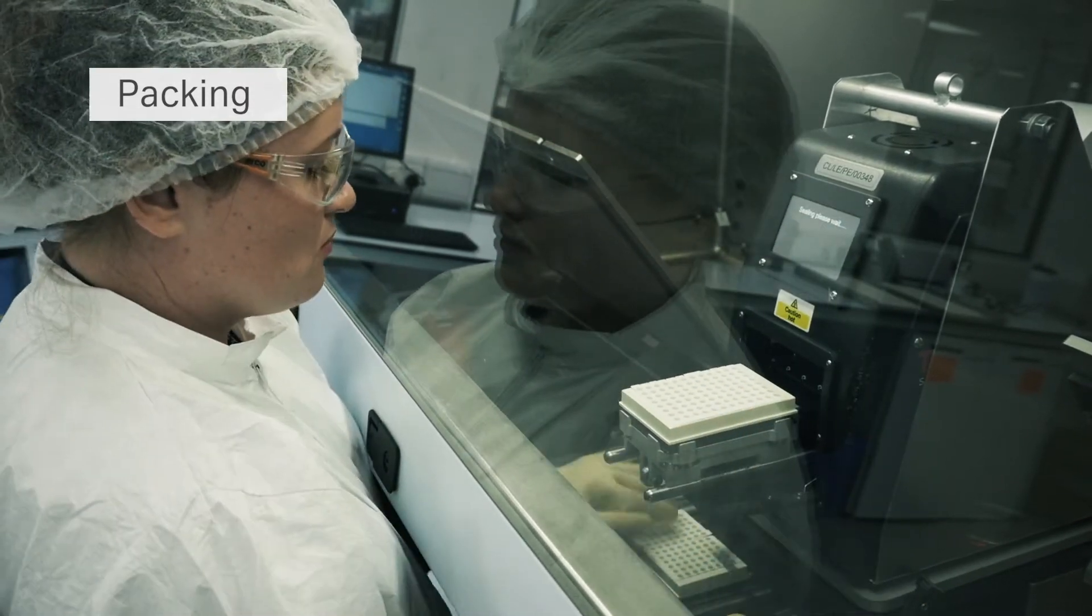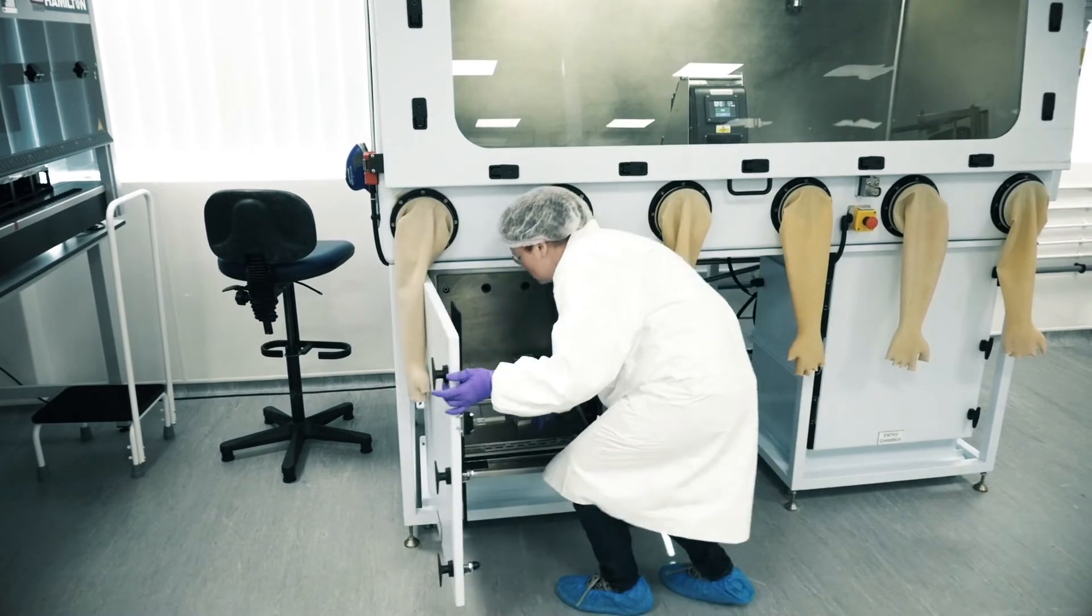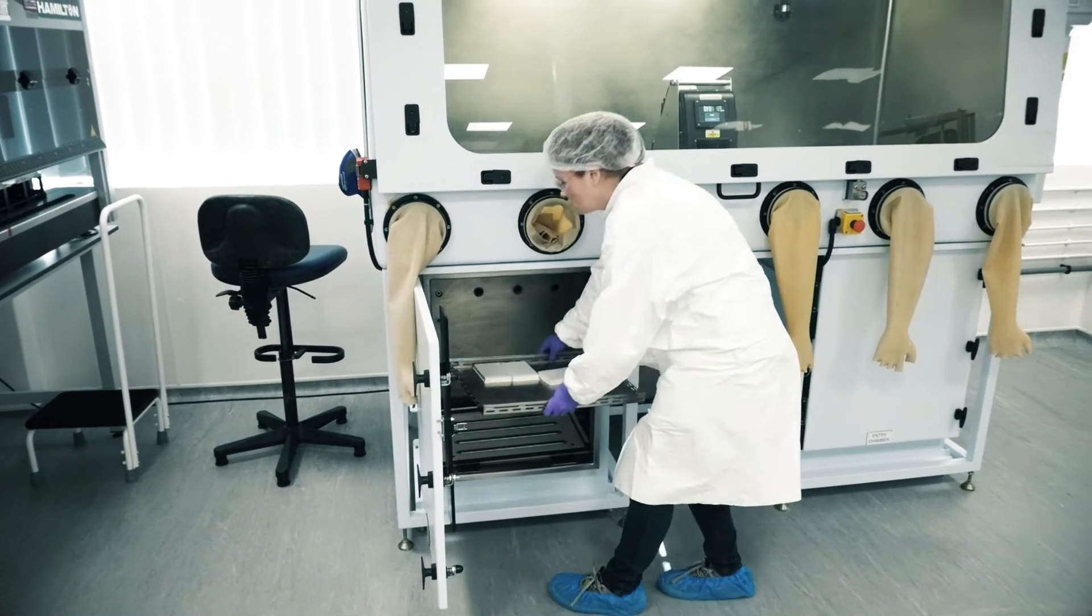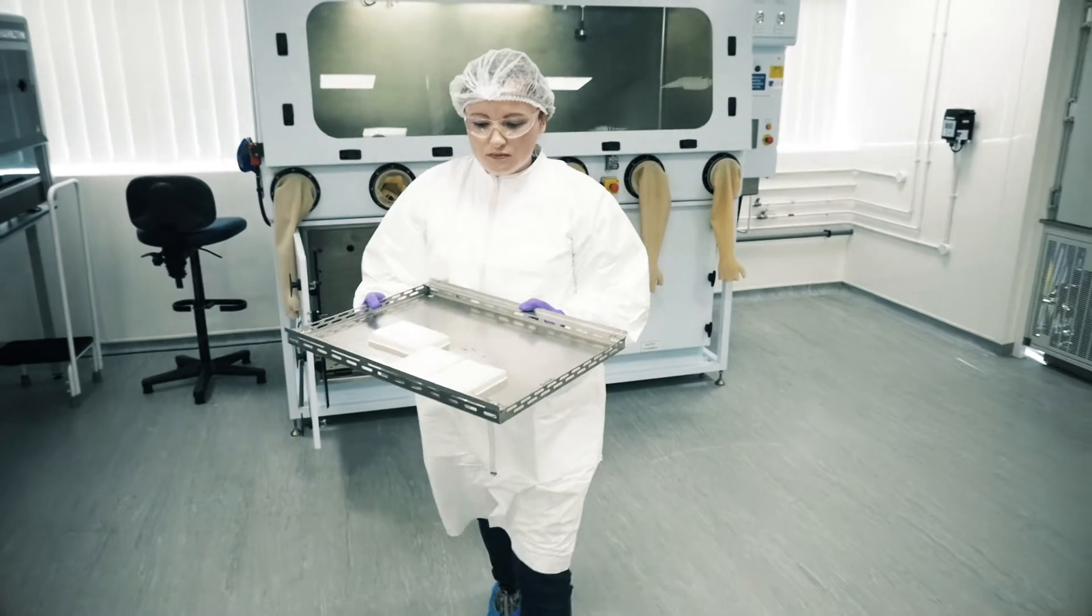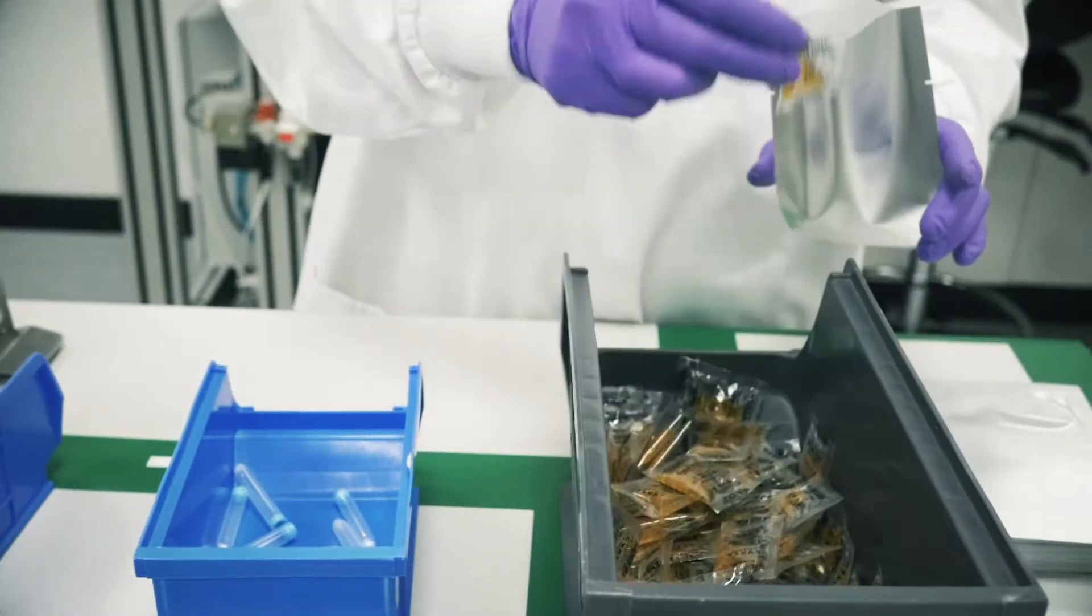We offer a range of sealing environments either in the freeze dryer itself, a nitrogen enclosure, or a very low humidity dry box. This not only reduces the absorption of moisture by the product but also provides an additional method to prevent contamination.